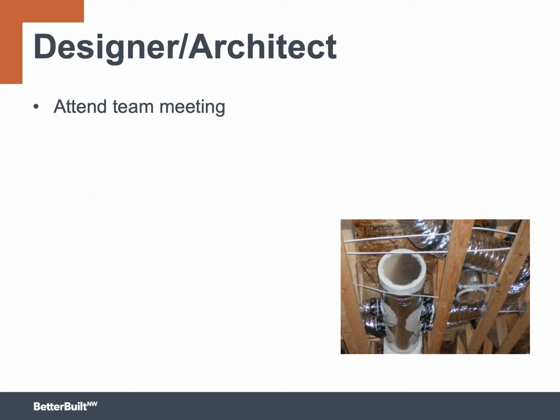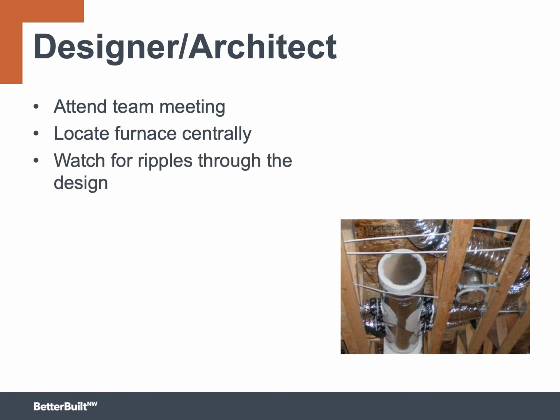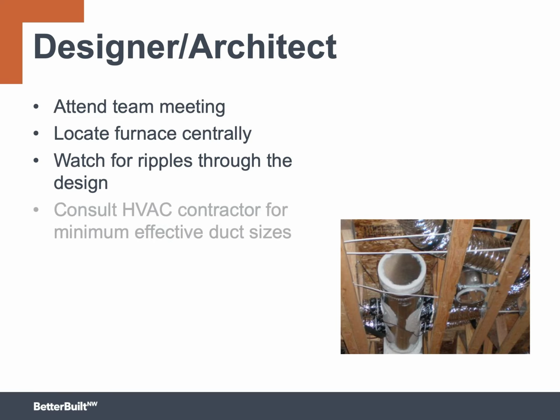The designer needs to position the furnace or air handler in a central location, and then think about how that location will ripple through the floor plan. Does it affect lighting fixtures, pipes, and wiring? Where are the supply registers going to be located? Consult with the HVAC contractor in order to make sure that those decisions make sense. And also, what are the minimum duct sizes that need to be accommodated in the building cavities?